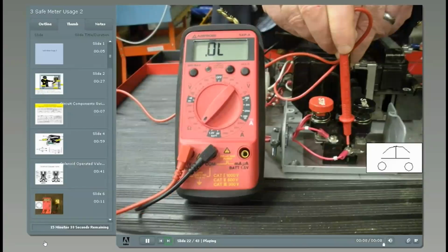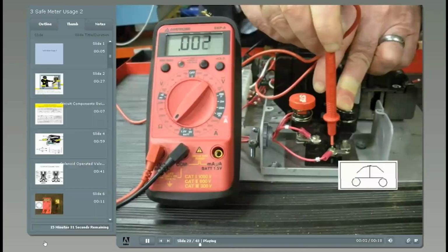this time. Ohmmeters require no power on the circuit, and it is important to isolate the circuit being checked from the rest of the circuit. Sometimes a wire needs to be disconnected in order to isolate. In order to completely check out a switch, it should be effective in both states, both open and close.